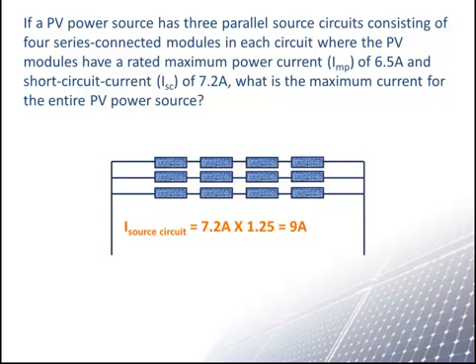For the entire photovoltaic power source, NEC standard 690.8A2 states that the maximum current is the sum of parallel source circuit maximum currents as calculated previously in 690.8A1. Therefore, since there are three parallel source circuits, the maximum current for the PV power source is three times the 9 amps or 27 amps.